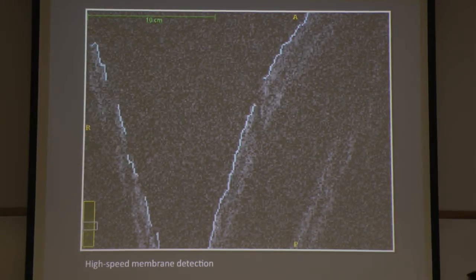Some of the first results that we've achieved here, this is on a phantom that has Scotch tape folded and embedded in gel. And if you look at this, you can see we basically have two bright lines here. This is the top and bottom surface of the piece of tape. And it was creased and folded, so we have a piece of tape here and then another piece of the tape here. Looking at this, you can see we have very low signal-to-noise ratio here. This isn't easy to see when we're doing this at very high frame rates. If we have more light on the camera, we can get better signal-to-noise, but as I said, our volume rate suffers.